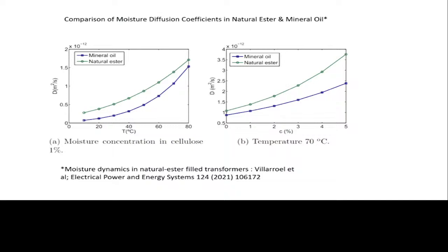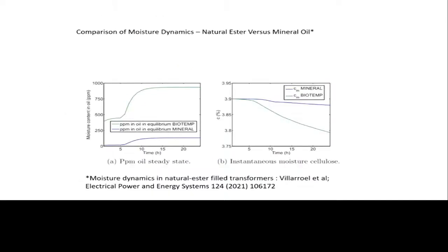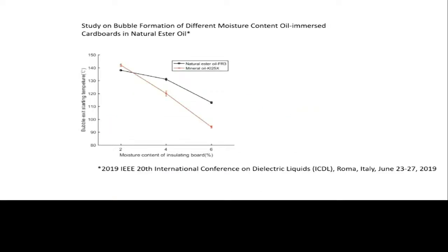So if the transition takes place very smoothly and very fast, as in the case of esters, the transition of moisture from paper to oil takes place very smoothly and in fact very fast in the case of ester oils. And so you are not going to see any partial discharge effects or bubbling effects, and all this within 30 minutes or so, within a few hours, sorry. Whereas in the case of mineral oil, even after several hours, it doesn't reach equilibrium.